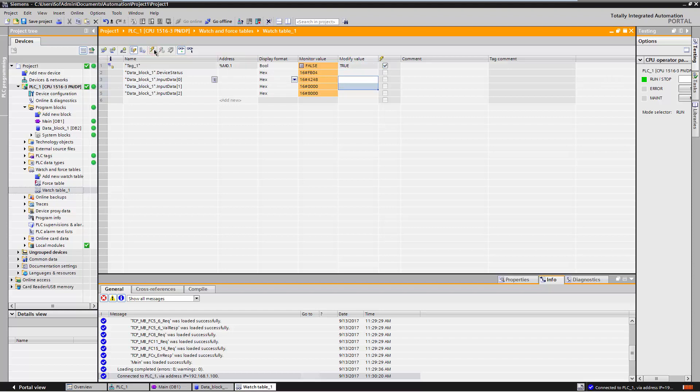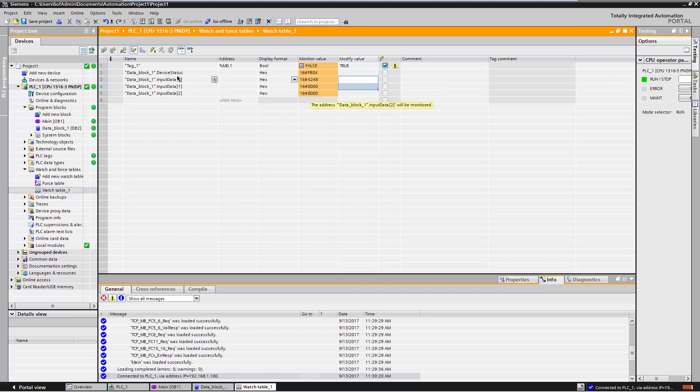The high byte of the status information is the so-called life sign. The value is incremented by 1 with each successful reading of input data from the device. The low byte describes the operating state of the device. The value 4 means that the device is in cyclic data exchange. The first two registers of the input data correspond to the value. The high byte of the last register contains the status. Hex 80 means good. If you click several times on Modify Now, you can see how the data changes.